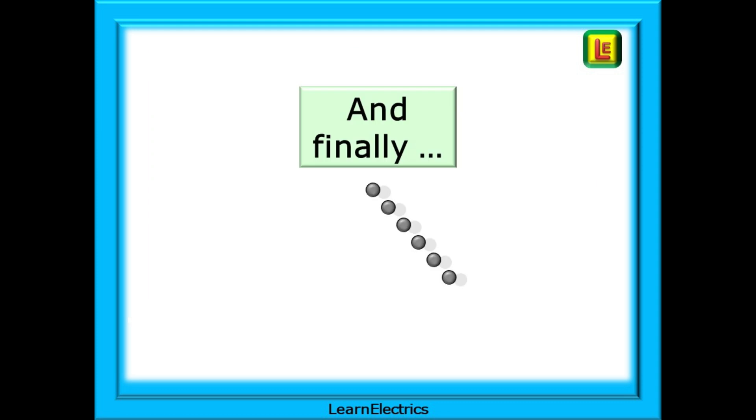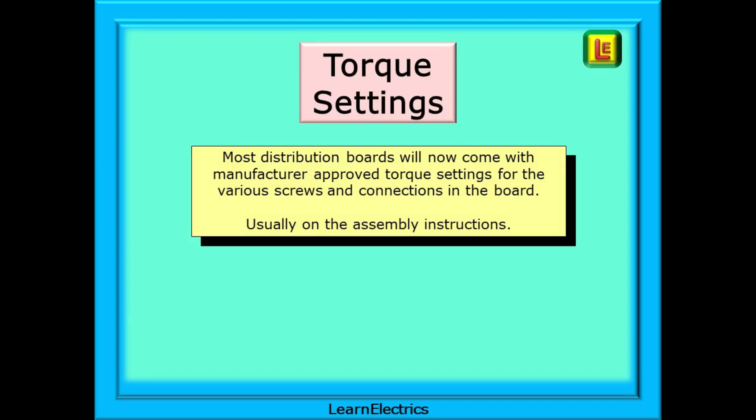And finally, a couple of points to finish on. The correct torque settings are becoming more important. Gone are the days when we did them up tight enough just by feel. So use a torque screwdriver. They're a good investment. Most distribution boards will now come with manufacturer-approved torque settings for the various screws and connections in the board. These are usually on the assembly instructions and sometimes the manufacturer has glued a label to the inside of the cabinet with the torque settings on it.